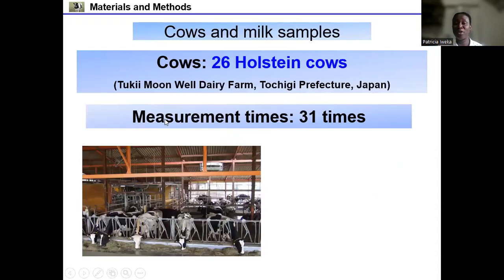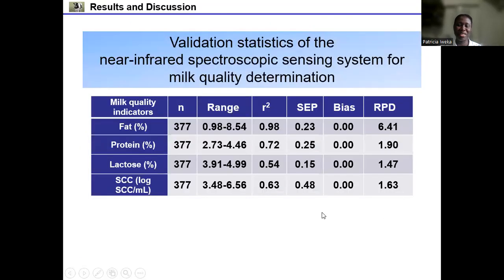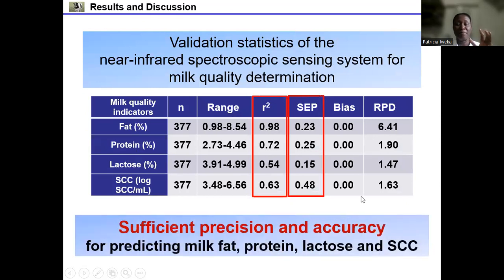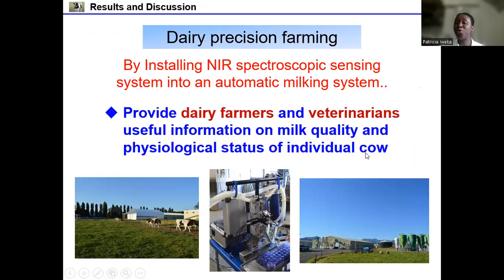Twenty-six Holstein cows belonging to Tukii Moon Well Dairy Farm at Tochigi Prefecture in Japan were used in this study. Measurement times were 31 milking times, and cows were used during their different lactation periods. The validation statistics for milk quality indicators showed that R-squared values for the three major milk constituent contents and somatic cell count were very good, and SEP values were also good. Sufficient levels of precision and accuracy were obtained for predicting milk fat, protein, lactose, and somatic cell count.